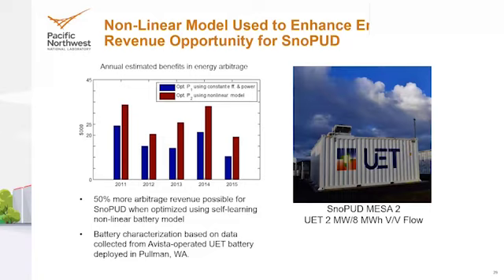What this shows you is for this one location, although it's quite a low value stream because arbitrage in the Pacific Northwest—the Mid-Columbia—is a relatively low energy market with very few broad swings between off-peak and peak prices, it's a low economic value. But using the nonlinearity in our modeling procedure, we actually generated much more value because we could charge the battery system in sweet spots to maximize the efficiency of those operations.